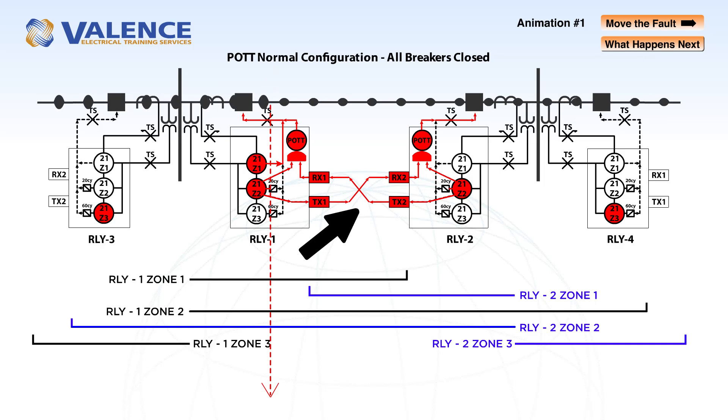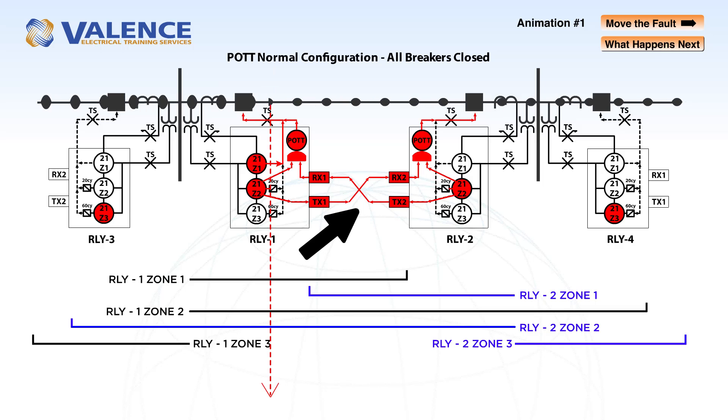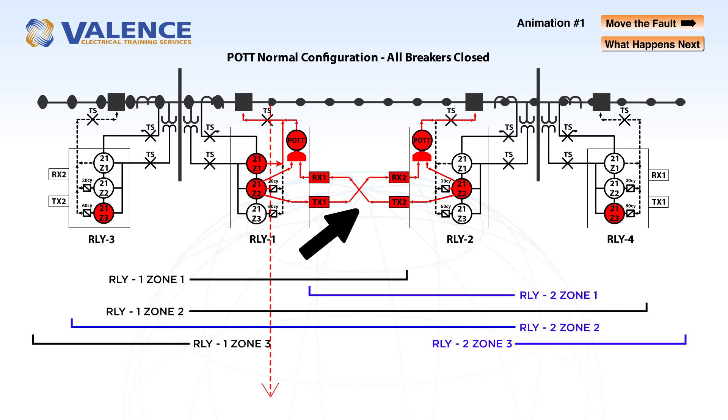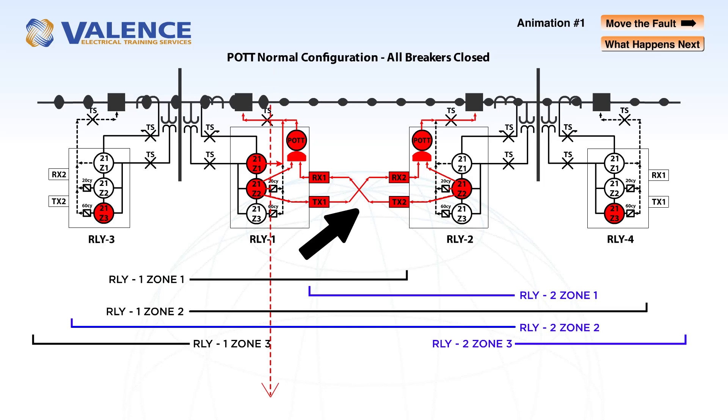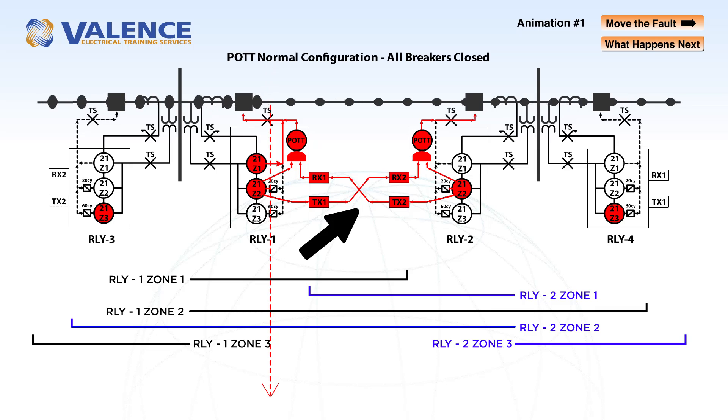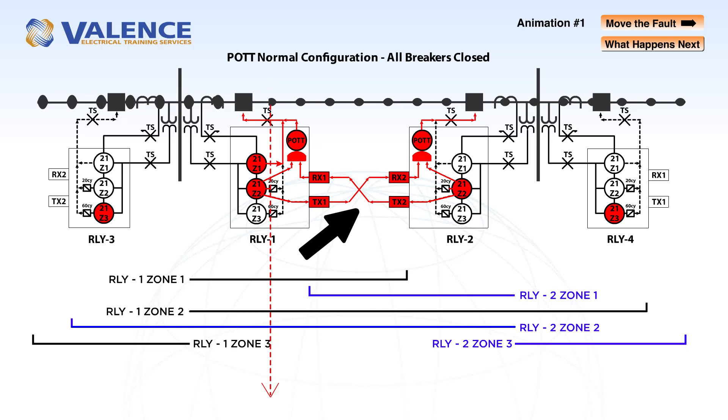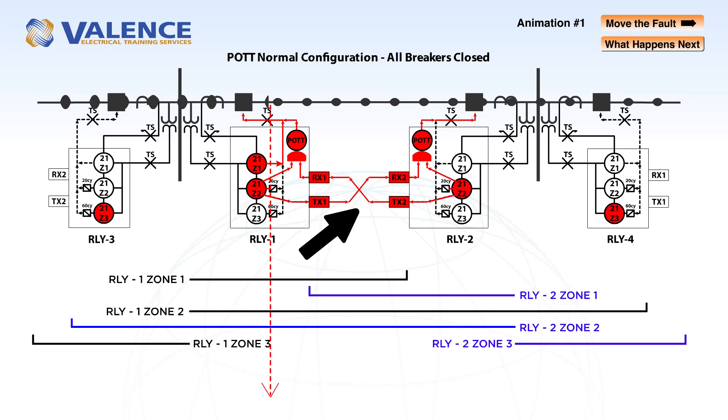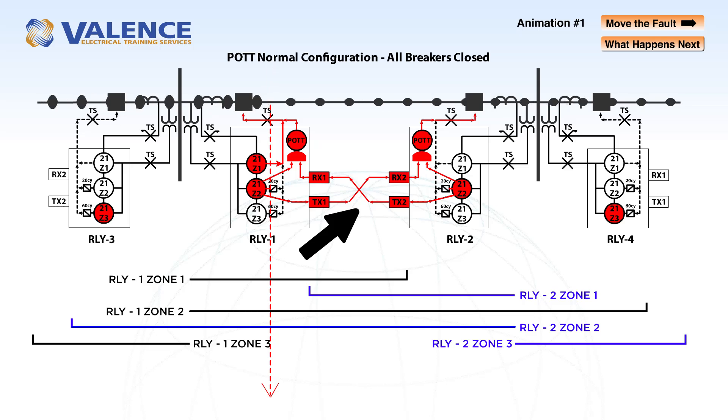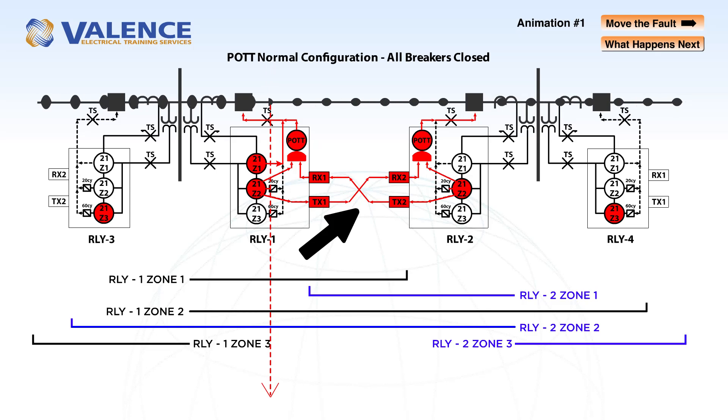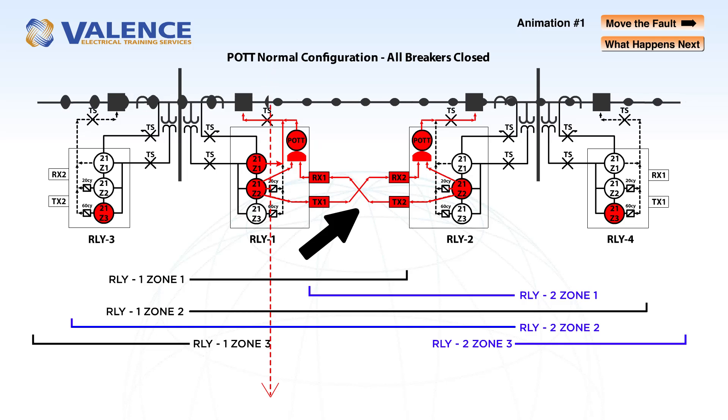A POTT scheme communicates zone 2 information between relays. If either relay detects a zone 2 fault, it will send a signal to the other relay. If the other relay also detects a zone 2 fault, the fault must be between the two relays, and there's no reason to delay in this case. Therefore, if a POTT scheme detects a zone 2 fault in both relays, both relays will operate as quickly as they can.